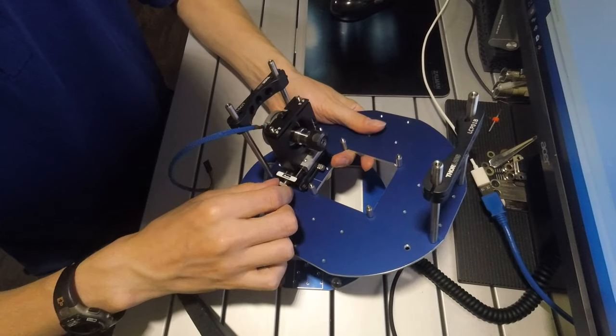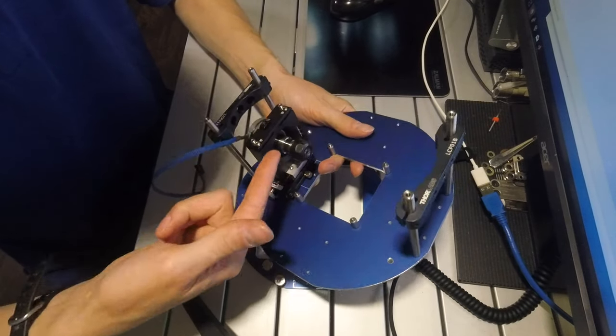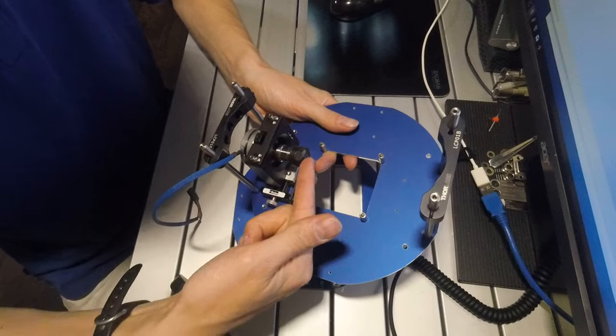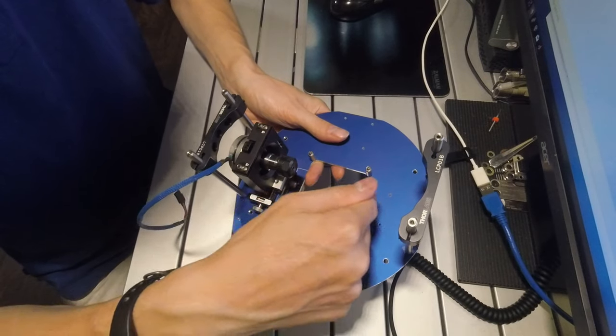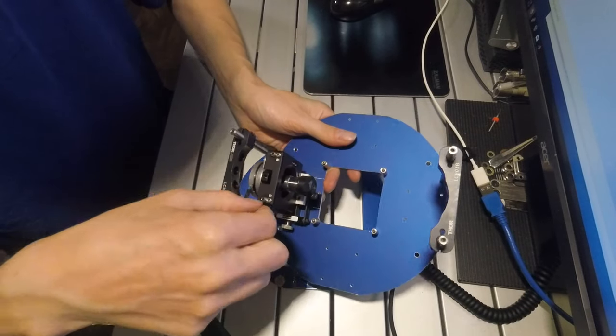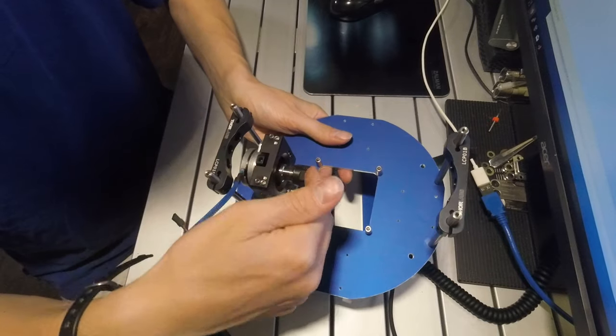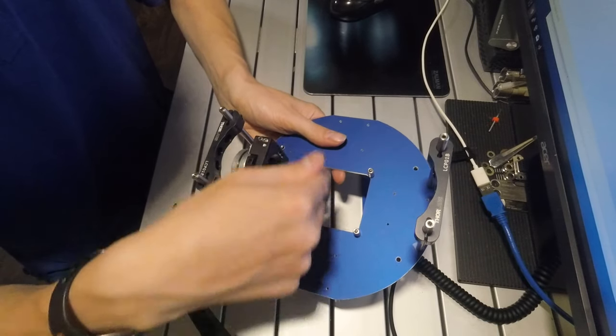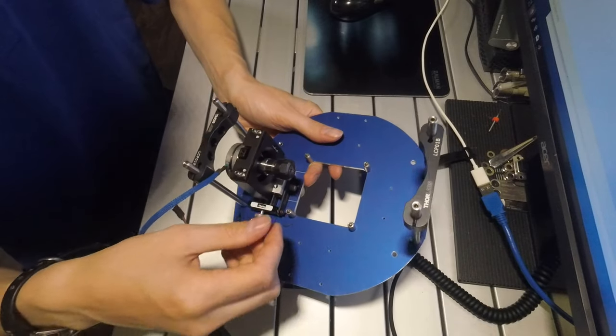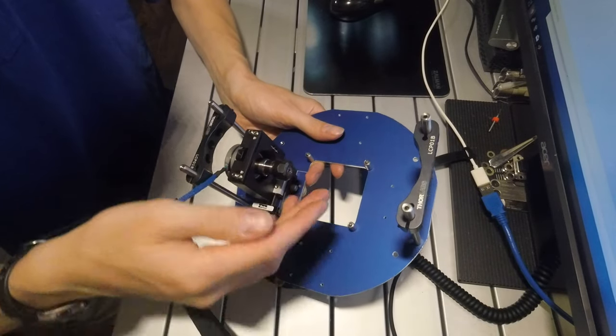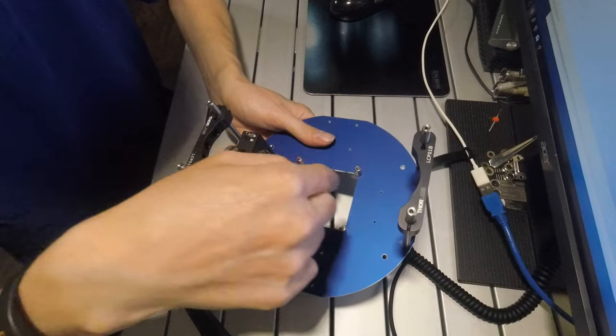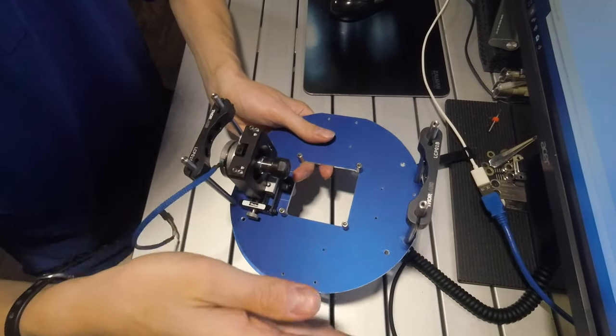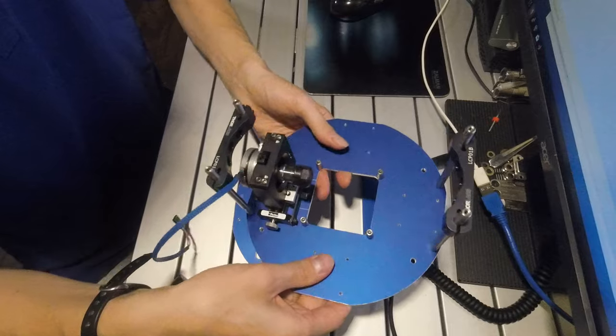So the Parker stage you can turn the adjuster knob and drive the stage in and out of the machine to align the center of the rotation axis with the center of the x-ray sensor and you can also adjust the tilt of the stepper motor up and down and left and right. So that not only is it aligned in the center but it's also aligned perfectly perpendicular to the y-axis of the sensor.